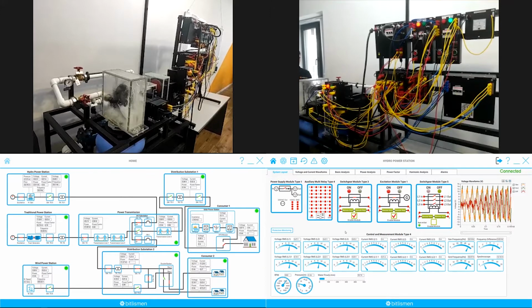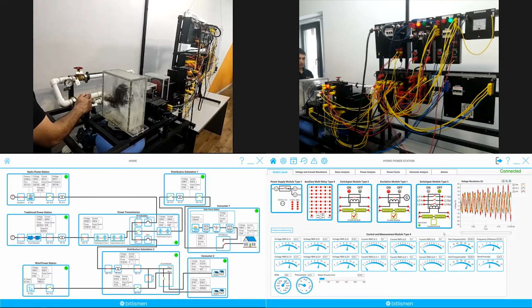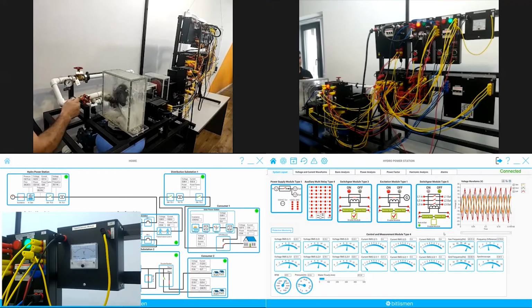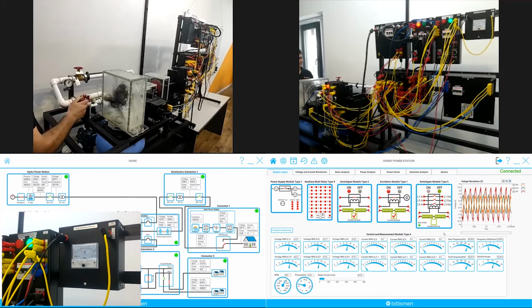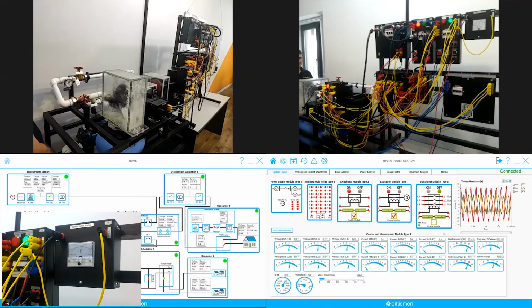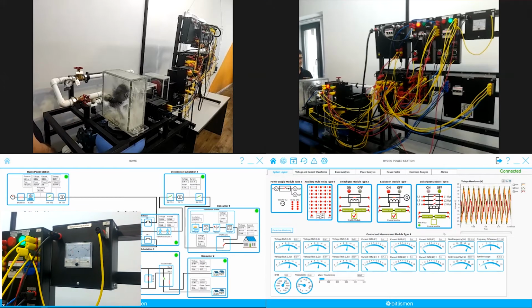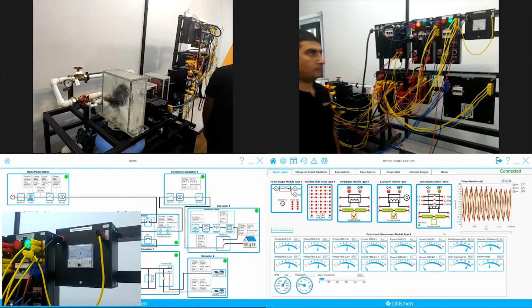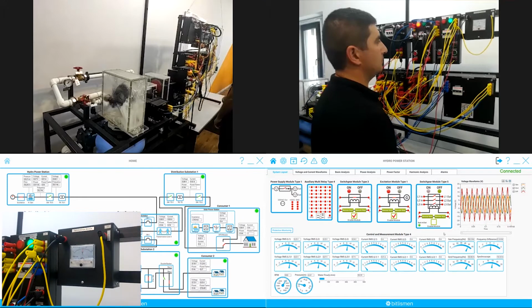At this stage, we need to regulate the voltage of the hydropower station. It should match the voltage of the microgrid. Here we can see that the voltage is more or less matching the microgrid voltage. And we also need to regulate the frequency of the hydropower station. Now we reach the frequency near to 50 Hz, which matches the frequency of the microgrid.